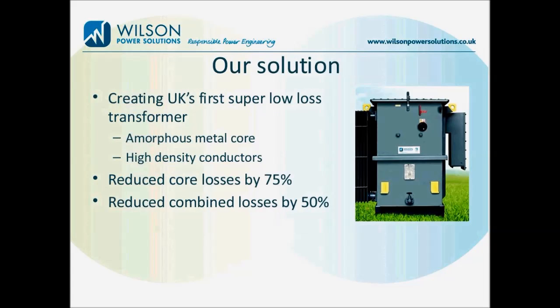There have been efforts to improve energy efficiency of transformers over the years in Western Europe and the US. So-called low-loss units would offer reduced load losses through use of conductors with a greater overall surface area. And also in countries where supply infrastructure is notoriously unstable, like India, efforts to reduce core losses permanently led to the development of core materials with better energetic profiles, such as amorphous metals.